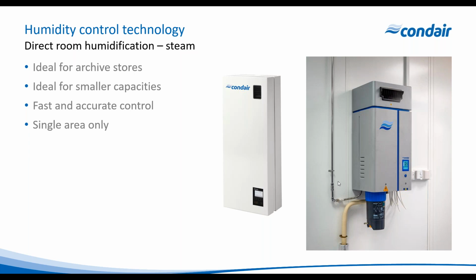Well, you can use an in-room system. And the one on the left here, that's just a small, up to 8 kilos an hour, steam production unit. And you've got a small orifice there for the steam to come out of, and then a control panel where you put in the set points and various other commissioning details. And for small archive rooms, these are really popular.